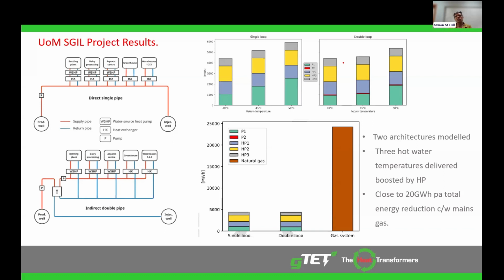As you can see on the top right, the parallel indirect loop, the traditional ring main system, is slightly more efficient. The y-axis there is a bit difficult to read, but that's basically the amount of energy you've got to put in to deliver the heating needs. We're assuming the heating needs are constant, and how much do we have to spend to get there. You can see, yes, it is better, but maybe not worth the capital cost of running duplicate plumbing everywhere and all the additional resources.